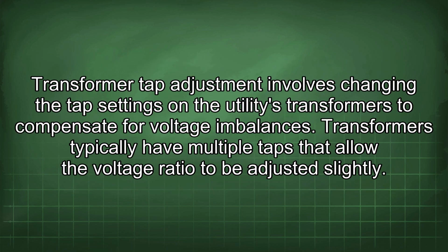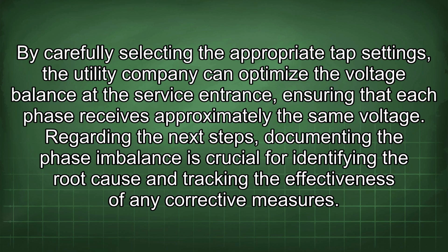Transformer tap adjustment involves changing the tap settings on the utility's transformers to compensate for voltage imbalances. Transformers typically have multiple taps that allow the voltage ratio to be adjusted slightly. By carefully selecting the appropriate tap settings, the utility company can optimize the voltage balance at the service entrance, ensuring that each phase receives approximately the same voltage.